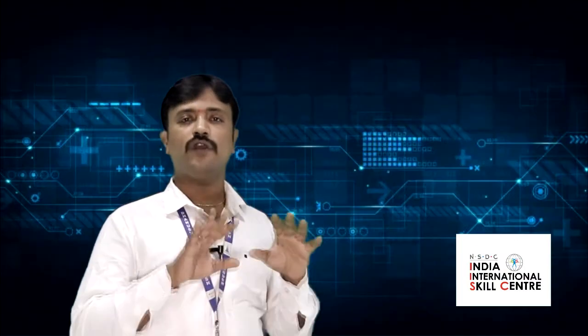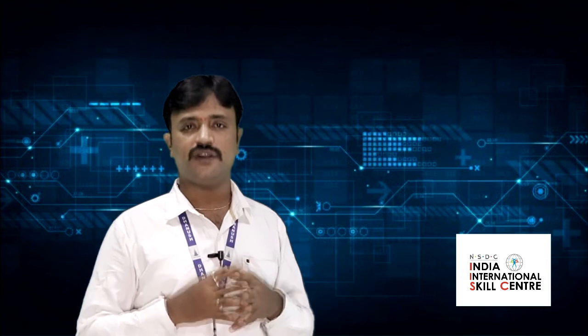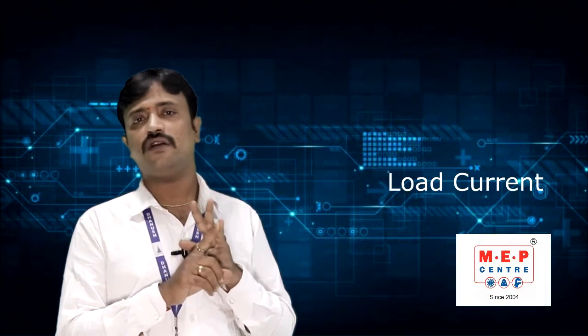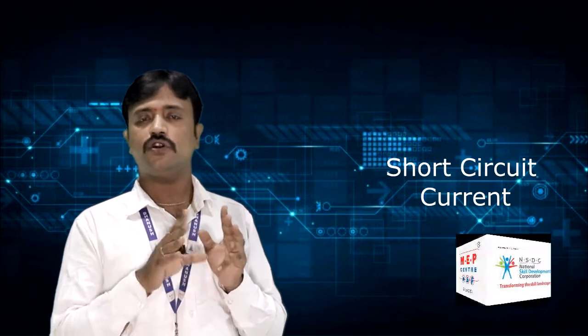Now, the question is, how are we going to select the circuit breaker for which ampere rating? So, in this module, we are going to study the circuit breaker calculation. Circuit breaker calculation is done based on three parameters. The first one is the load current, based on which we need to select the circuit breaker. The second one is based upon the short circuit current. Now, what is short circuit current?